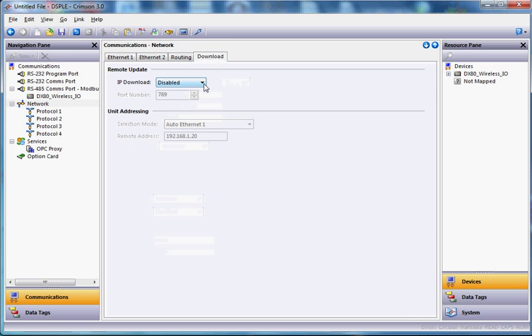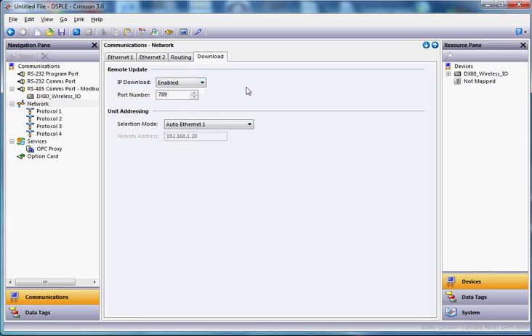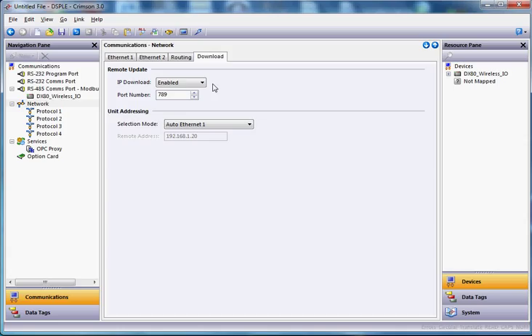If I go to the download tab here, I'll just point this out to you. This is kind of cool. If you enable this, your first download of the product will be via USB cable. But if you've got this turned on, and you have a compact flash or an SD memory card in the Red Lion product, you can then subsequently, next generations or next revisions, download over Ethernet instead of USB, which is a nice feature. But you have to have a compact flash card or a SD memory card in the Red Lion product to be able to do that. That's because if your firmware is different than your version of Crimson 3 is different than what's running on the Red Lion product, then we need a place to cache memory while we upgrade or downgrade the firmware in the actual Red Lion product.